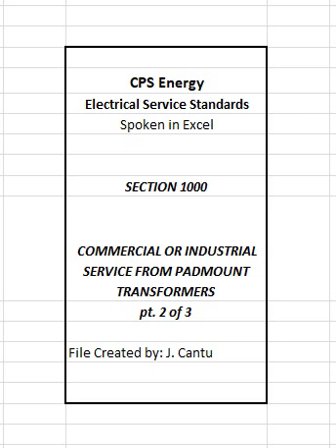7. Tap box shall be a standalone enclosure that is weatherproof and constructed of minimum 12-gauge corrosion-resistant steel, primed and painted. 8. All tap boxes shall have a step bus arrangement in accordance with Figure 1001 and be designed to allow for equalizing the length of cables on each face. Busbars must have sufficient number of 9/16-inch holes, non-threaded, to accommodate lugs for connecting the source and service entrance conductors. Lug mounting holes shall have the standard NEMA vertical and horizontal spacing of 1 3/4 inches.